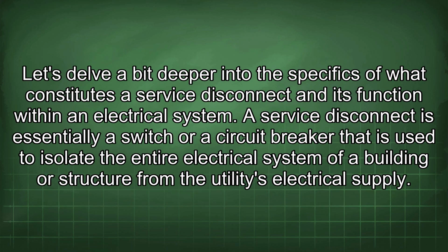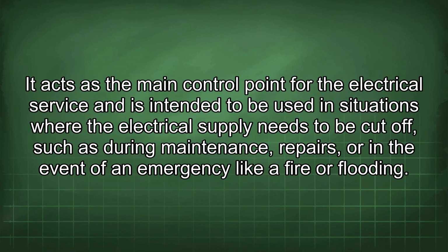Let's delve a bit deeper into the specifics of what constitutes a service disconnect and its function within an electrical system. A service disconnect is essentially a switch or a circuit breaker that is used to isolate the entire electrical system of a building or structure from the utility's electrical supply. It acts as the main control point for the electrical service and is intended to be used in situations where the electrical supply needs to be cut off, such as during maintenance, repairs, or in the event of an emergency like a fire or flooding.